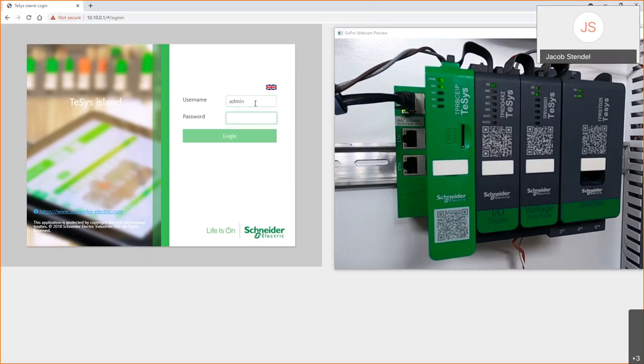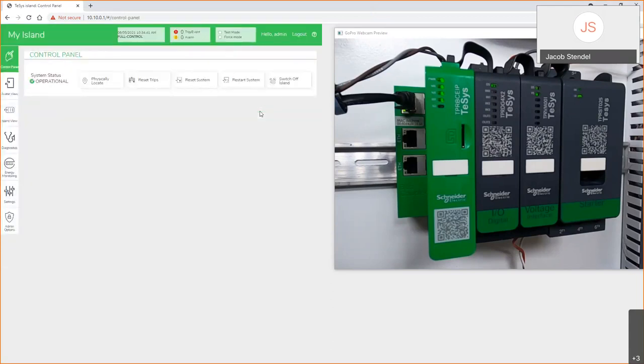I'm going to begin by logging in here. Look on the bus coupler. The top port is my terminal port. That's how I'm going to access it here. You can have user groups and rights assigned to what each operator or manager or technician can see and control on the TeSys Island, which is important because sometimes you don't want them to be able to configure set points or alarms. You only want them to view it. So this is what you see when you log in here.